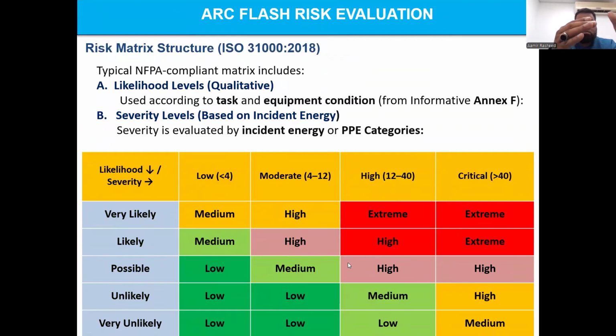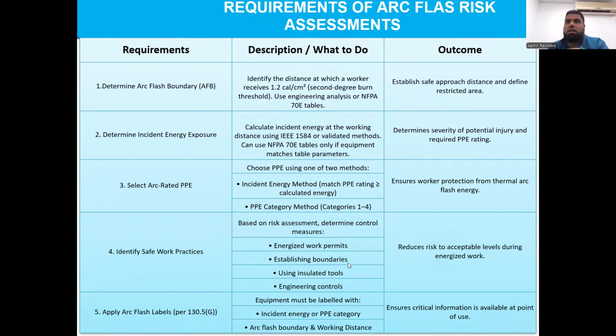In this matrix, you can see the likelihood as well as the severity. Likelihood basically depends upon the task and equipment condition, and severity depends upon the incident energy or the PPE categories. So risk evaluation, as I said, is a combination of likelihood and severity. It helps us to determine whether our risk is high, medium, or low, and accordingly we provide our control measures. This ensures that decisions are defensible, consistent, and risk-based. That's how it comes in there.